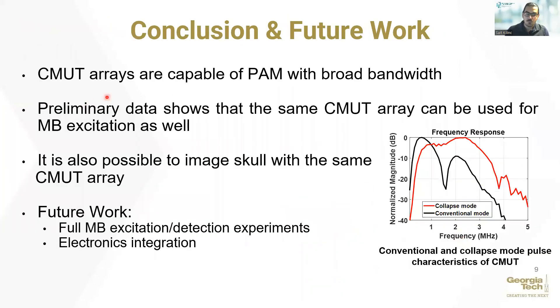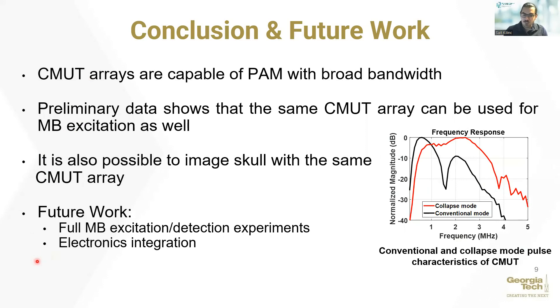In this study we demonstrated that CMUT technology can be used for passive acoustic mapping. The preliminary data shows we can utilize CMUT arrays for therapeutic excitation. Furthermore, with applied higher bias voltage we can operate CMUT in collapse mode, which means higher frequency operation. This mode can be used for skull imaging. For future work, full therapeutic excitation and detection experiments with the six CMUT arrays will be performed, and electronic integration with CMUT arrays will be investigated in detail. Thank you for listening, and I would like to take questions.